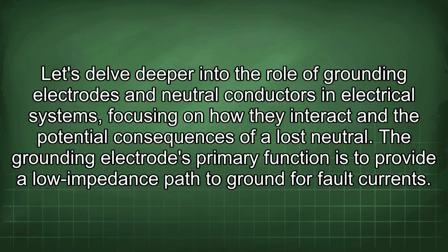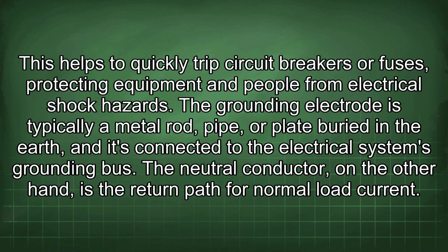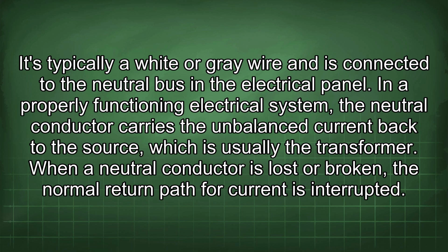The grounding electrode's primary function is to provide a low impedance path to ground for fault currents. This helps to quickly trip circuit breakers or fuses, protecting equipment and people from electrical shock hazards. The grounding electrode is typically a metal rod, pipe, or plate buried in the earth, and it's connected to the electrical system's grounding bus. The neutral conductor, on the other hand, is the return path for normal load current. It's typically a white or grey wire and is connected to the neutral bus in the electrical panel.